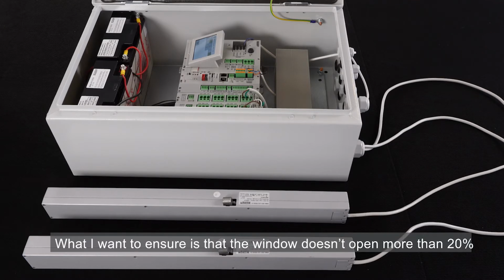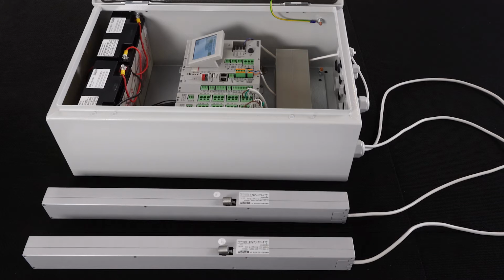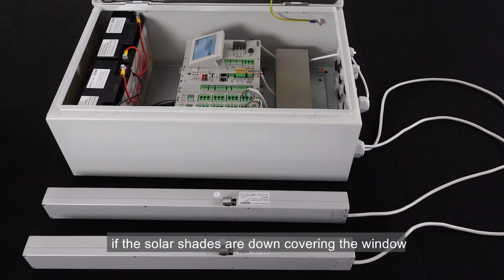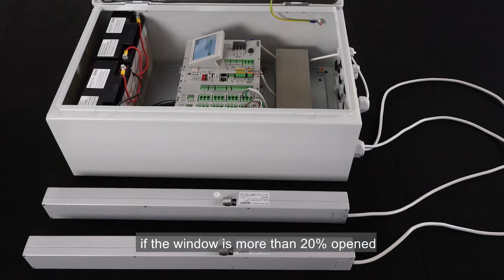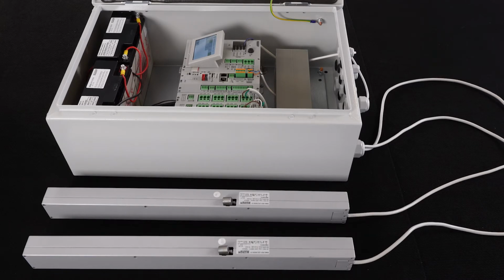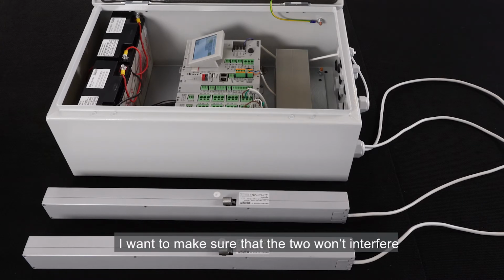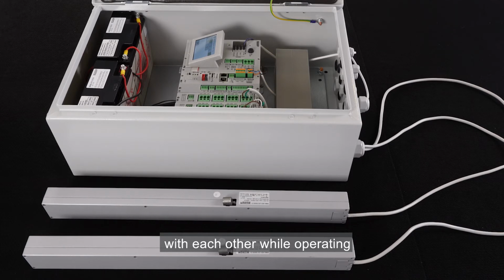What I want to ensure is that the window doesn't open more than 20% if the solar shades are down covering the window, and that the solar shades will not go down if the window is more than 20% opened. In other words, I want to make sure that the two won't interfere with each other while operating.